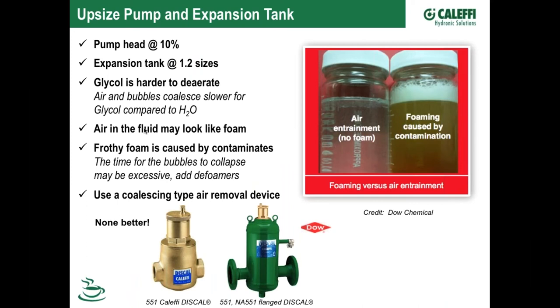This is a good point, and I've had this brought up to me a couple times: it's harder to get air out of glycol. You can see in this picture it's harder to purge. Glycol manufacturers actually put an anti-foaming agent in as one of the ingredients, because it tends to get a frothy mix when you start putting it through a centrifugal pump. A Caleffi discal does a good job of getting that out, but it might take a few days more.